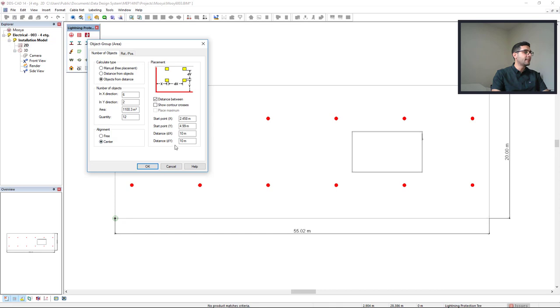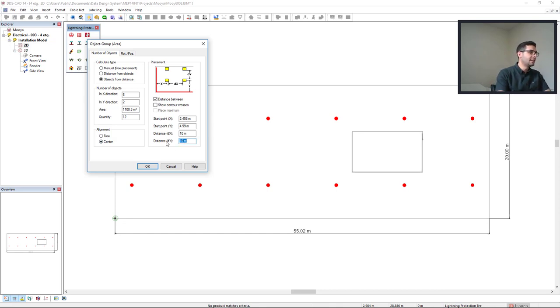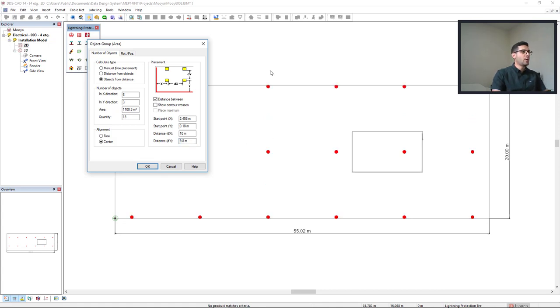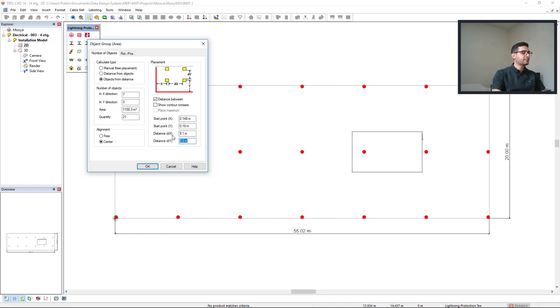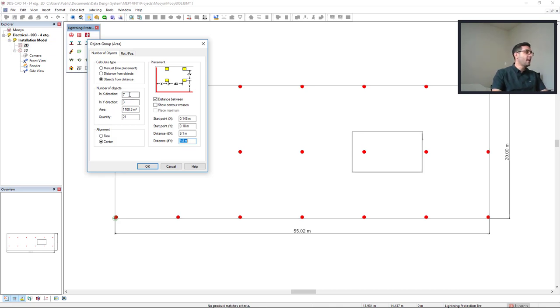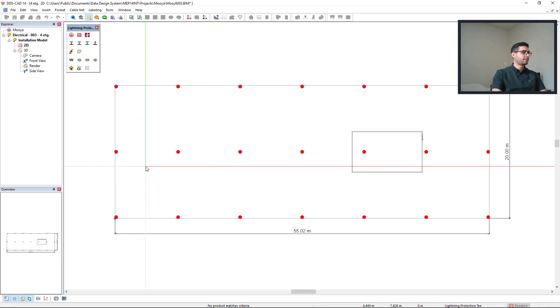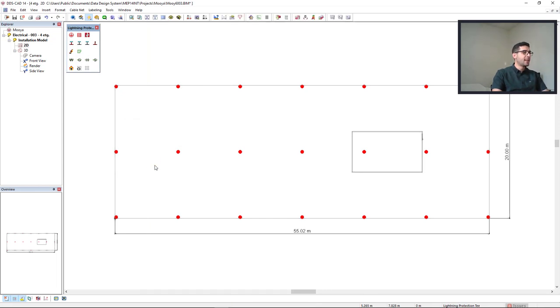To optimize this, I decrease the distance in the dy to 9.8. Press tab and we have one more row and in the dx I will insert 9.1 and I have also a new column. So at the end, I would like as calculated to have seven conductors in the x direction and three conductors in the y direction. Now we'll click ok and escape to close that function.